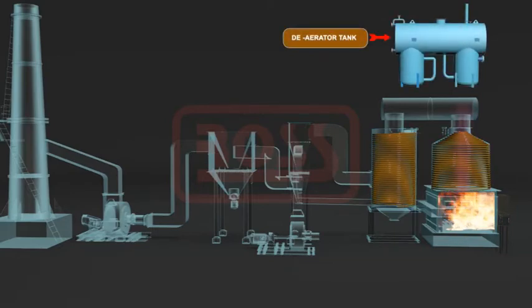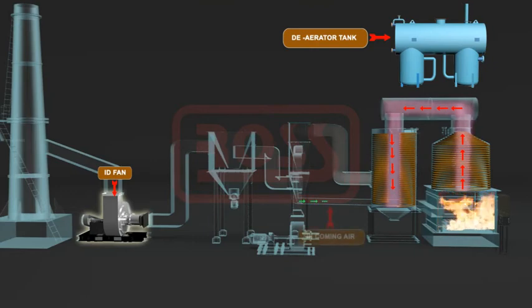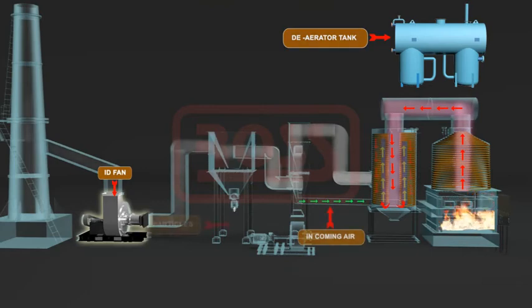Thermal oil pump is started. Fuel bed prepared on the grate bars is ignited manually and ID fan is started to provide necessary air draft for combustion. Furnace is thus heated up and hot flue gases pass through radiant and convective sections for heat transfer before exiting to atmosphere through a chimney.